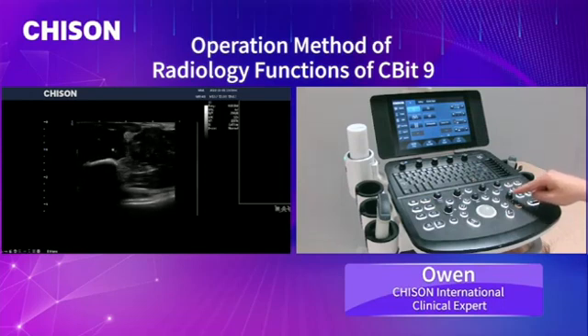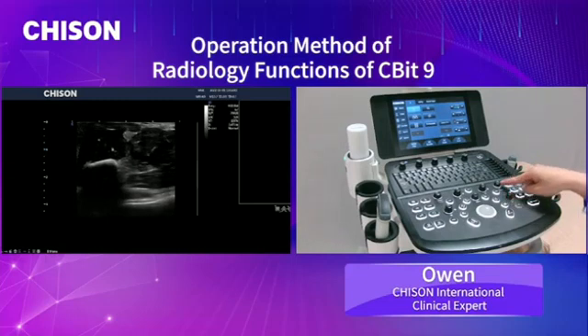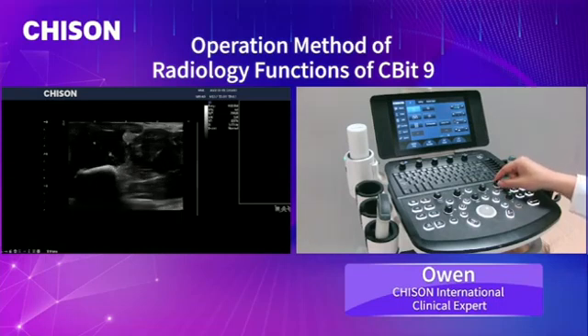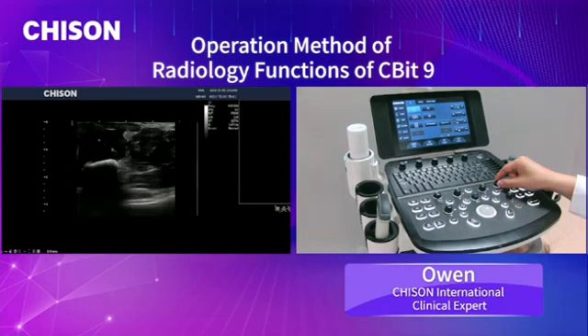And you can see these B buttons. We can rotate it to change the total gain, the brightness, and you can see the depth key here. You can rotate it slightly to change the depth according to the different body size, and you press it to change the focus position, which can increase the resolution of the focus area.